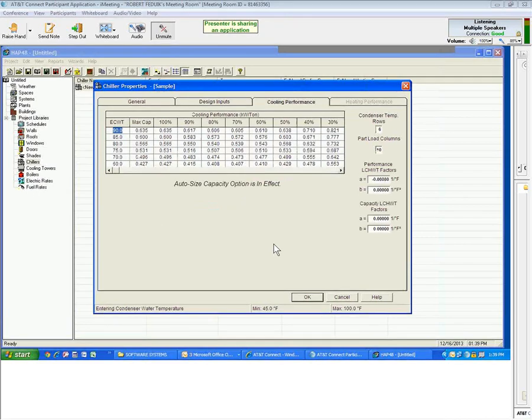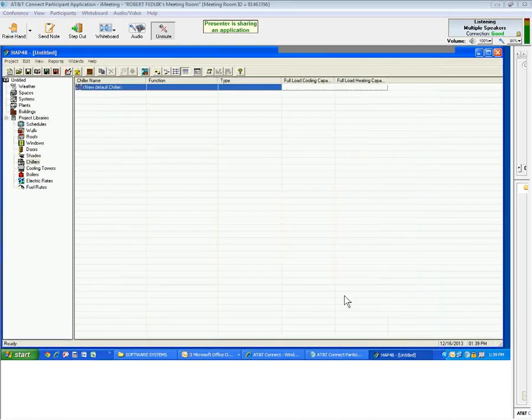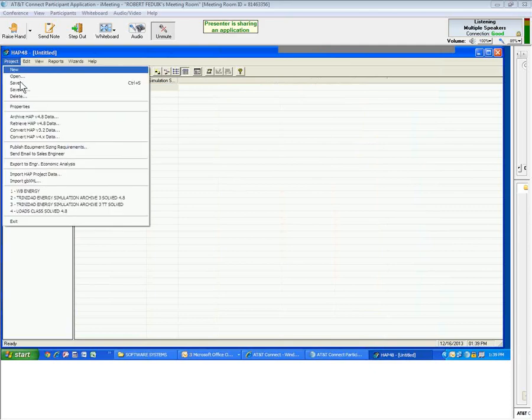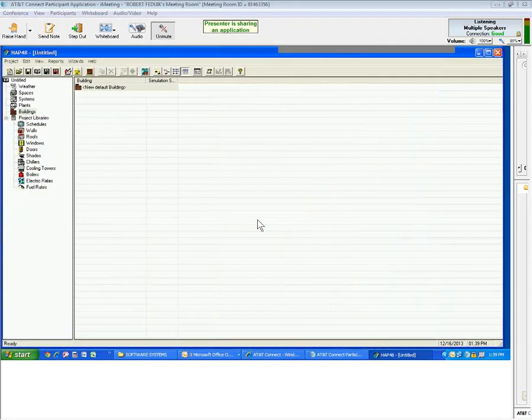And then I will generate part load data I think is representative of a starting chiller at 0.6 kW per ton. And I'll go ahead and run your operating costs with that data in it. So you get to know a lot about what you want to run an op cost on, or you get to know very little about it. It'll accommodate both situations. At the building level, and I'm just going to go open a project that has a building in it.